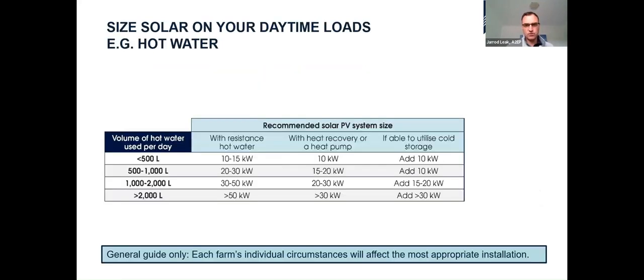I'm going to jump over this one and just give you a few quick tips. We mentioned matching your energy demand with the energy production from the solar - this is one way you can do some checks. If you just have an electric resistance hot water system and you're using somewhere between 500 and 1,000 litres of hot water per day, a 20 to 30 kilowatt system is going to be a fairly good size to deliver the majority of that energy. If you've got a heat pump, you can use a smaller system - it may be best to invest a little more in the heat pump and have a smaller solar system, especially if you don't have the space for a big solar system on your existing roof.